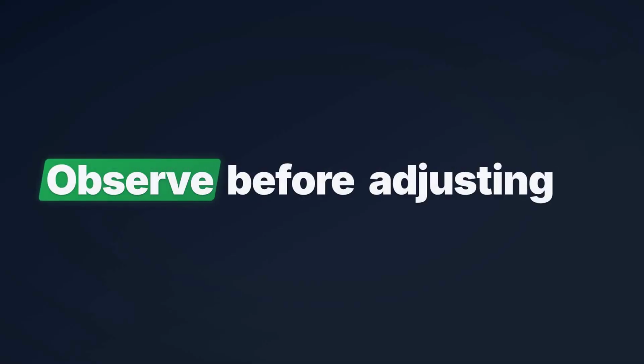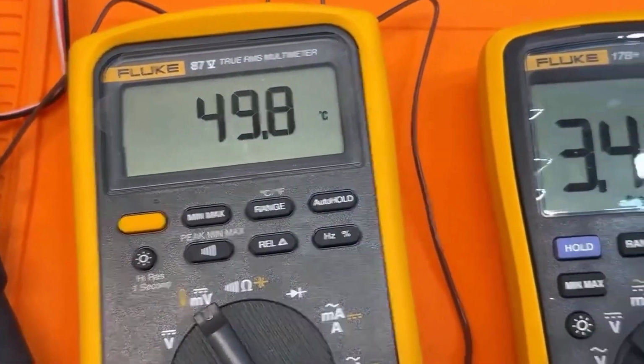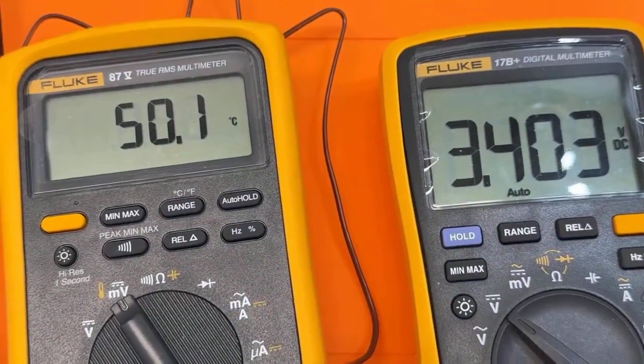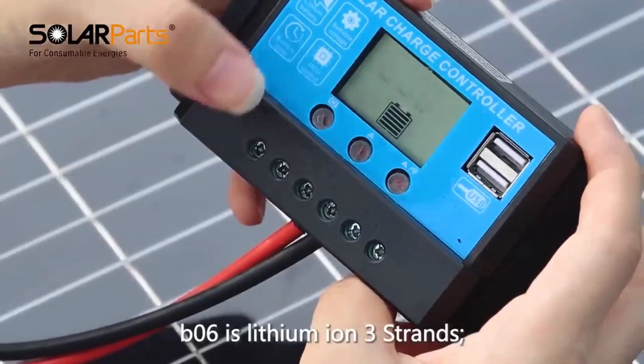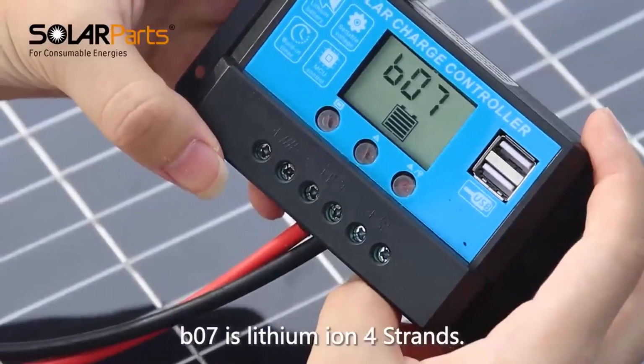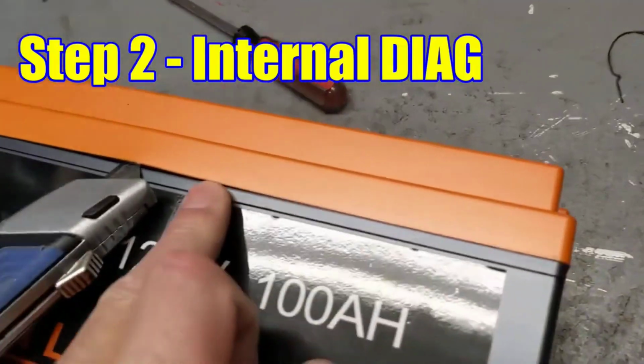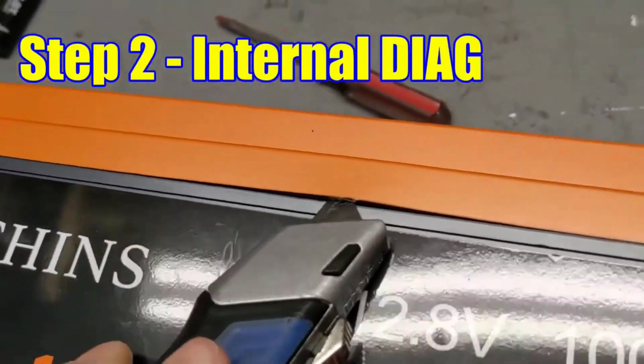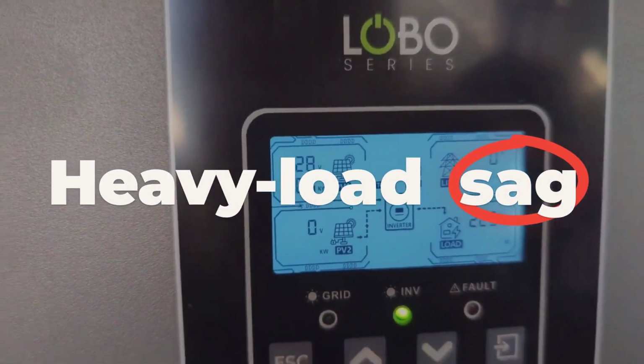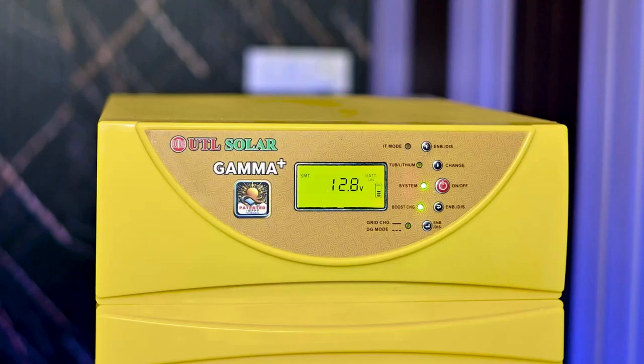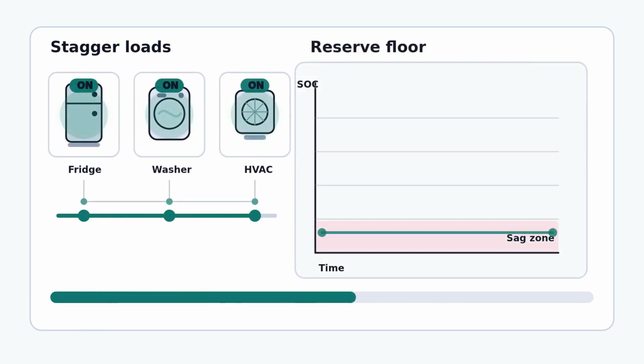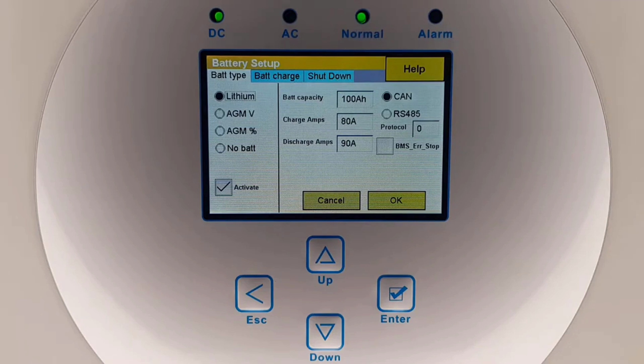Start with a simple diagnostic. Note the load size when shutdown happens, the battery voltage under that load, the displayed state of charge at the moment of cutoff, and whether the battery recovers normally after you remove the load or finish a charge cycle. Those 4 observations tell you almost everything. If shutdown only happens under heavy loads, the problem is voltage sag under peak draw. Your options are to reduce those peak loads, stagger them, or raise the discharge floor enough that the battery enters that high draw moment with more buffer above the sag zone.